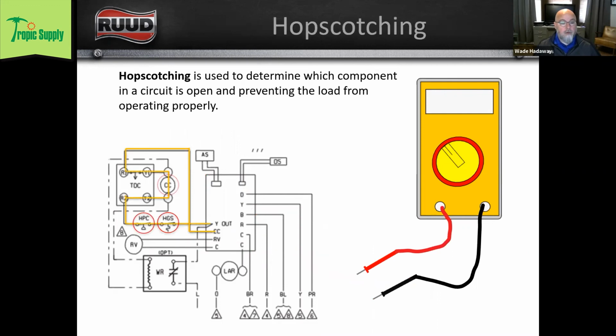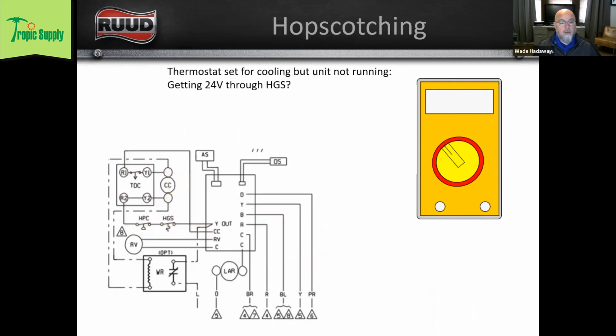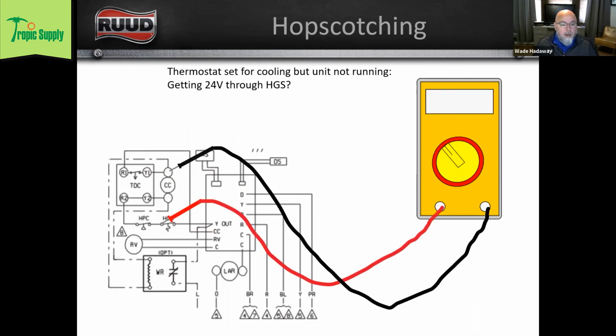So what I'm going to do is start at Y, and I'm going to look across my first switch. Am I getting 24 volts through the hot gas sensor? And I read 24 volts. Yes, I am. So the contactor is not energized, but I've got 24 volt potential, right? I've got 24 volts of electromotive force through my hot gas switch. So I know that switch is closed.